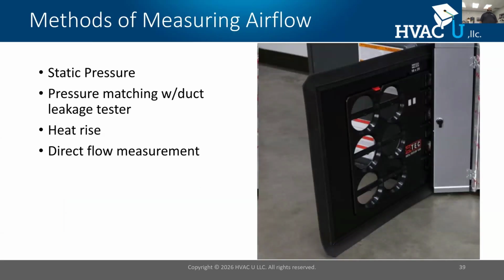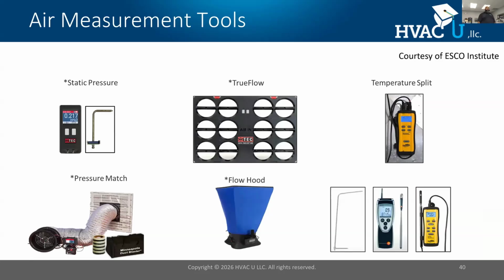All right, let's talk about measuring airflow. Oftentimes, when you're chasing an airflow problem, the first place I really need to start is: is the system producing enough airflow for the rated equipment capacity? All right, so we got a few types here. We got static pressure, we got pressure matching, we got a heat rise where we can use a formula, and we can have direct airflow measurements like you see here with a flow grid.